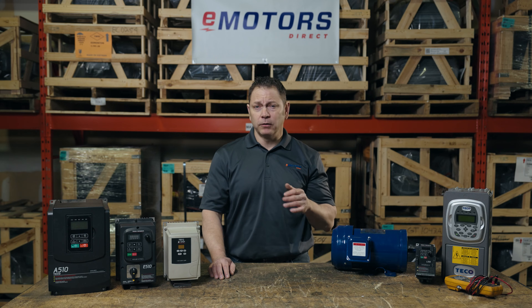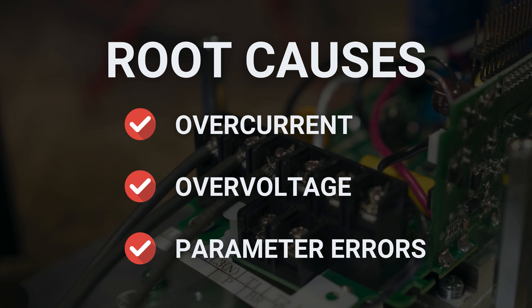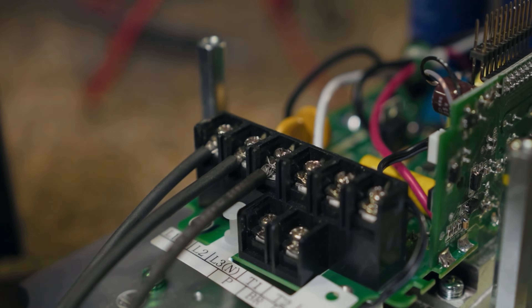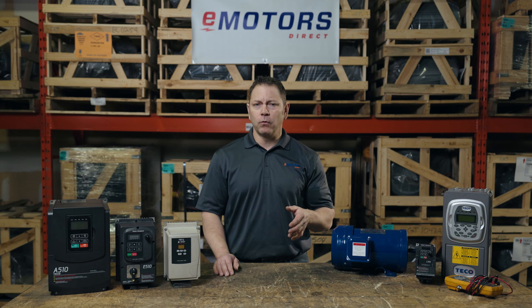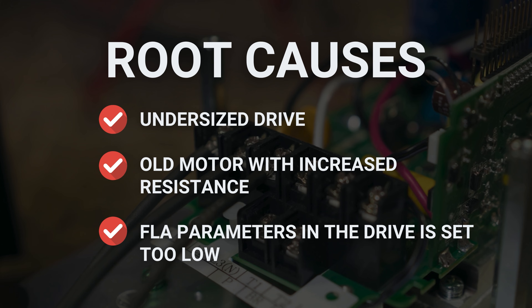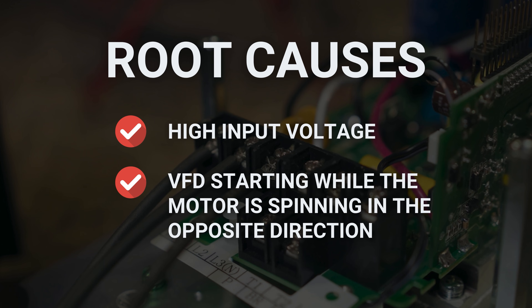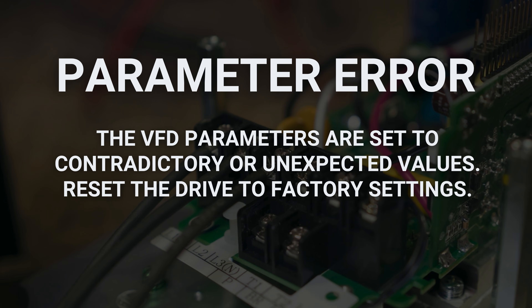Some drives won't start without a motor connected, so keep that in mind. Common nuisance failure fault codes include overcurrent, overvoltage, and parameter error. An overcurrent state is caused by the motor asking for too much current — this might be caused by an undersized drive, an old motor with increased internal resistance, or the motor full load amps parameter being set too low. Overvoltage occurs when the DC bus voltage exceeds its rating, often caused by high input voltage or the VFD starting while the motor is spinning in the opposite direction — common for outdoor fans. A parameter error is usually caused by parameters set to contradictory or unexpected values; reset the drive to factory settings and see if that fixes it.